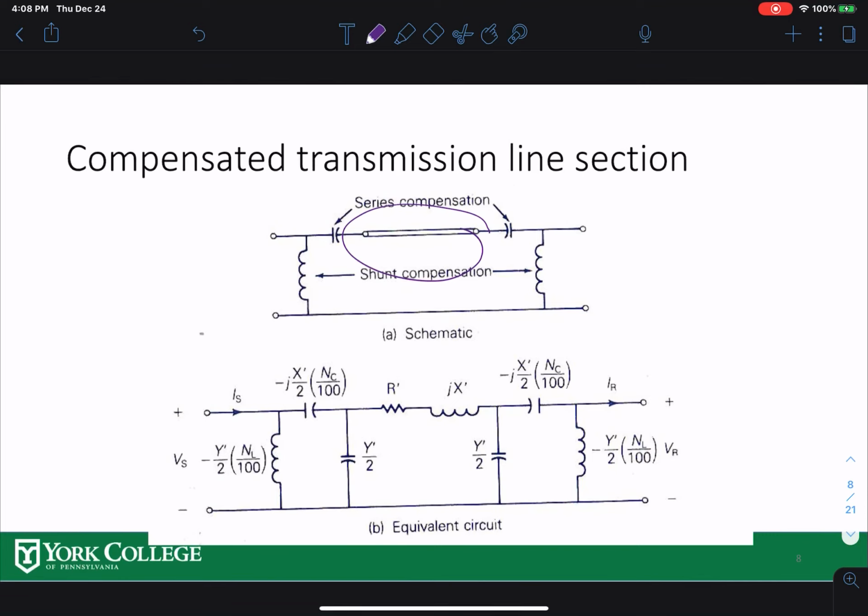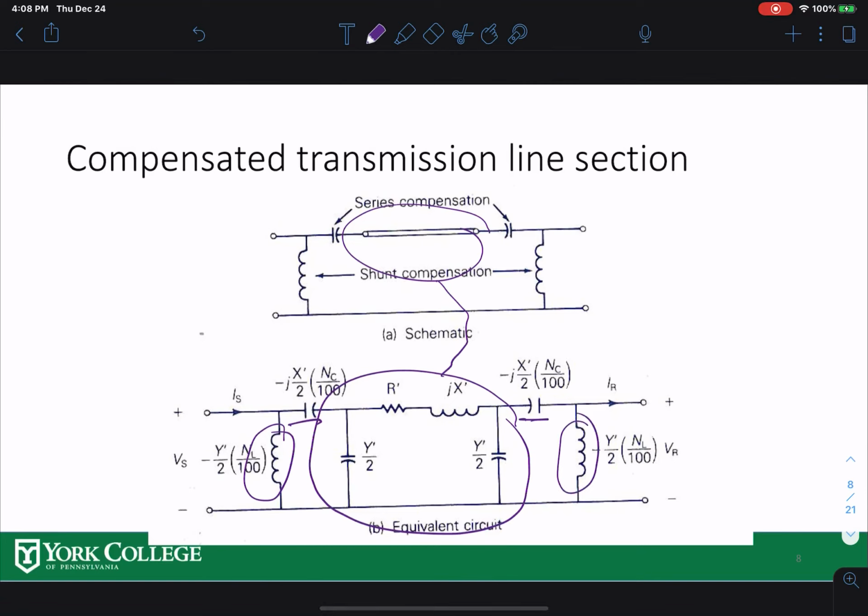So now you have the transmission line over here. Then your series compensation over here, and your shunt reactor over here. Then your capacitor compensation could be added to this one over here, or it could be right here. So that's your compensation line. Compensation is done to support the voltage in the line because of no load, light load, or fully loaded conditions. We're going to stop here for today for this part, and we're going to see you for the next part.